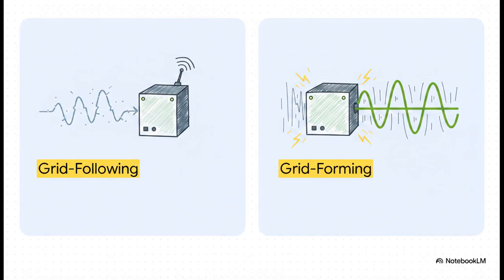Building on that truck analogy from earlier, the standard grid-following inverter relies entirely on a strong grid to stay synced. If the grid gets weak, it can lose track and just destabilize. But the grid-forming inverter, it doesn't just survive in a weak grid, it actually injects strength right back into it. By creating its own ultra-stable reference point, a GFM leaves the electric grid in a much better, more resilient condition than it found it. It is literally software replacing steel. The whole goal here is to make the grid feel heavy and stable enough to survive sudden chaos.